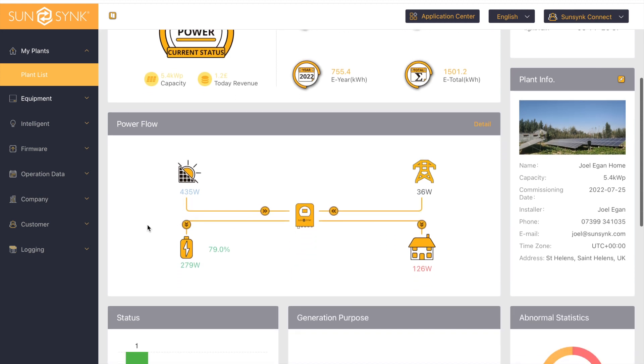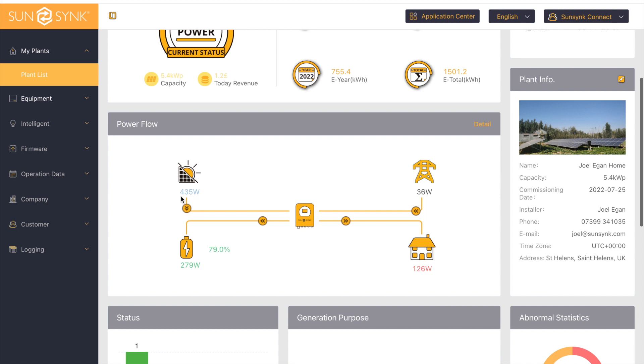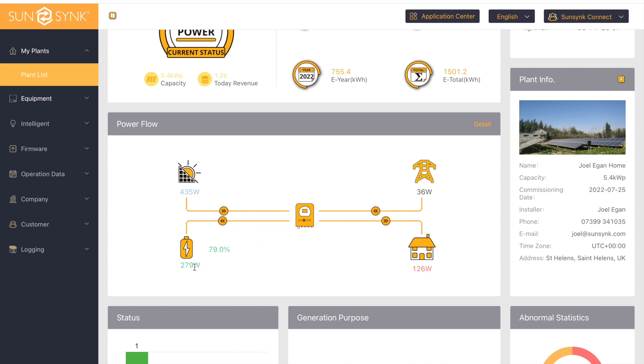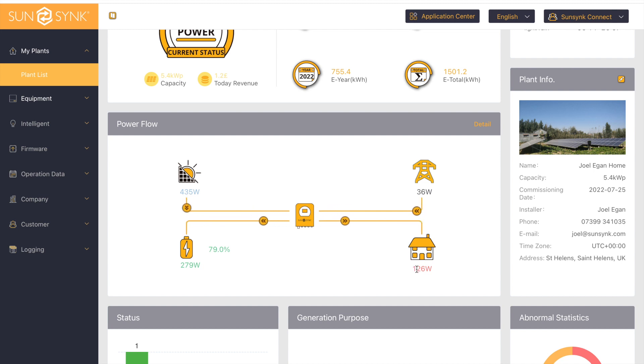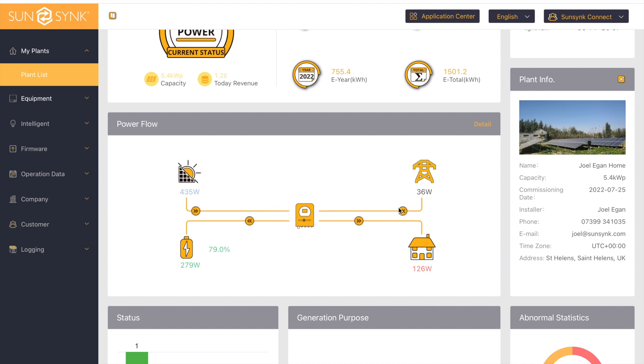If we go down to the power flow, this is an overview of what is happening with your system at the moment. You can see at the moment I'm generating 435 watts, 279 watts is going back into the battery, the battery state of charge is currently at 79%, there's 126 watts going to the house, and there's 36 watts coming in from the grid. This is just a grid trickle feed to prevent feedback.